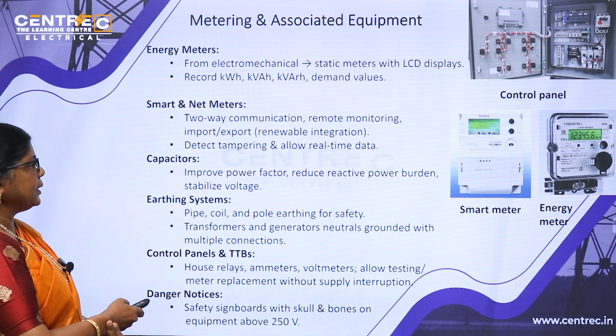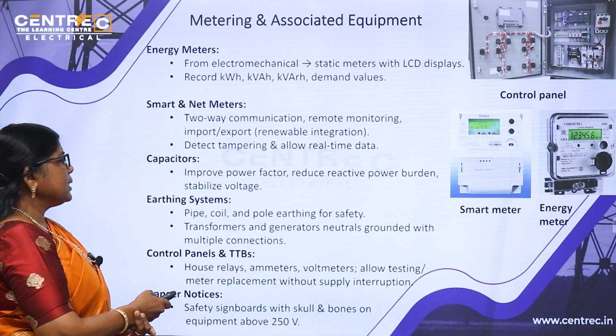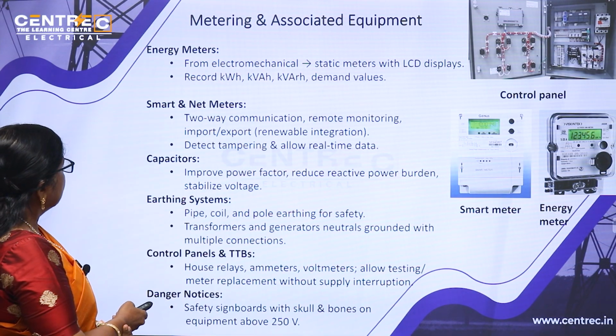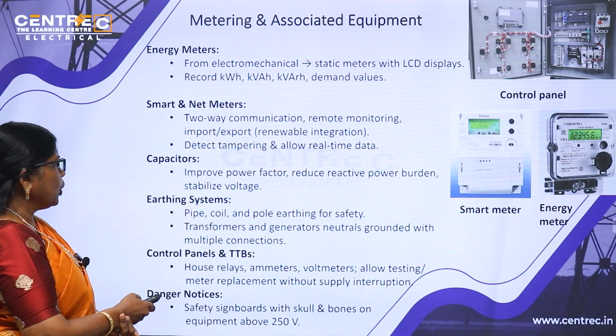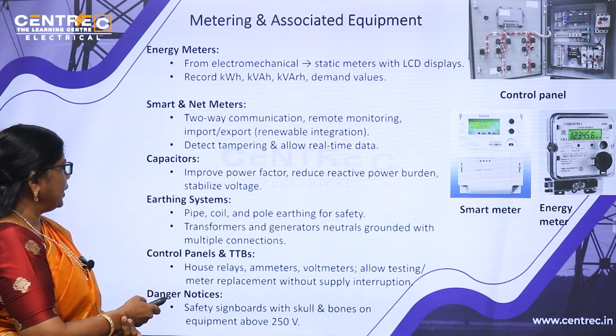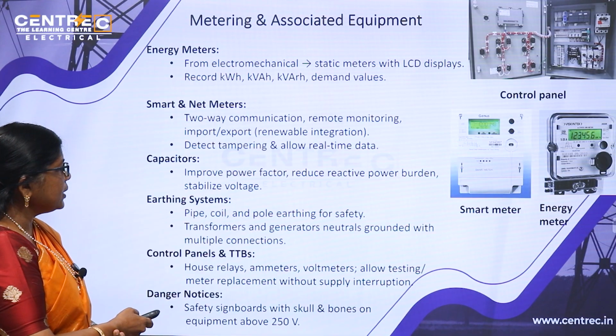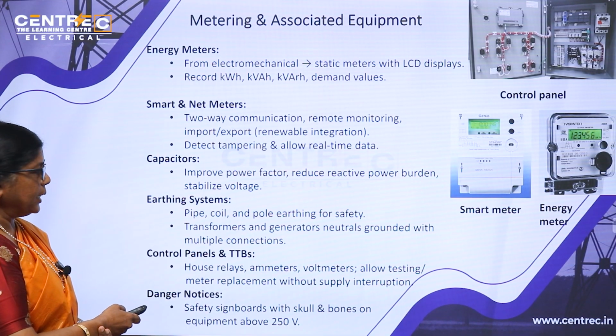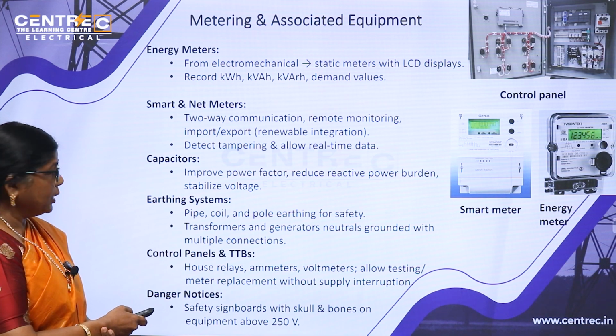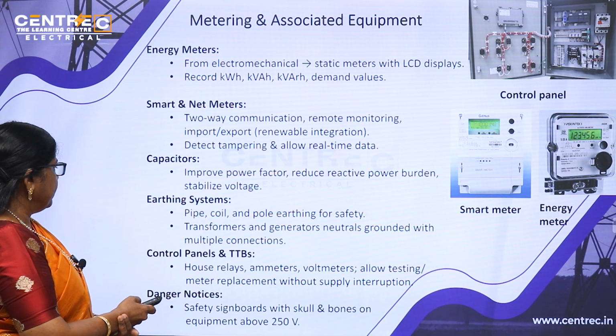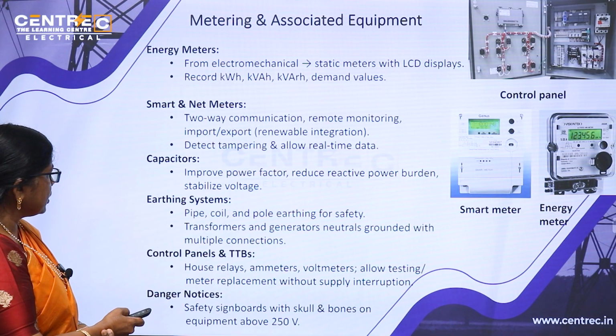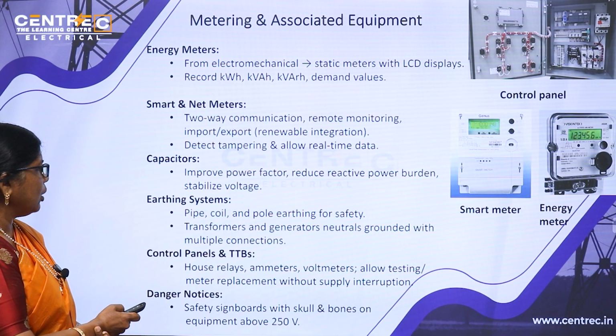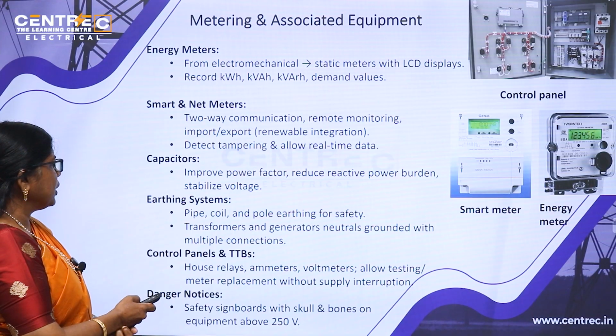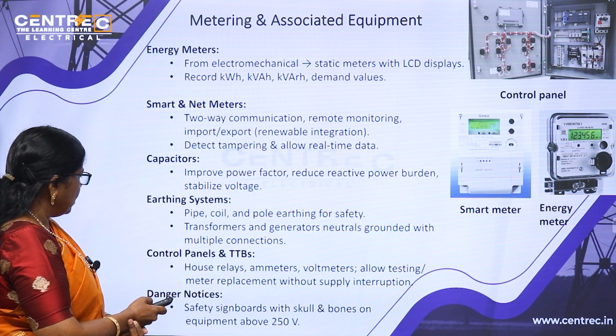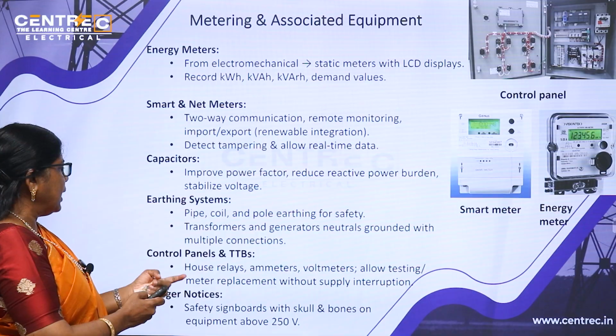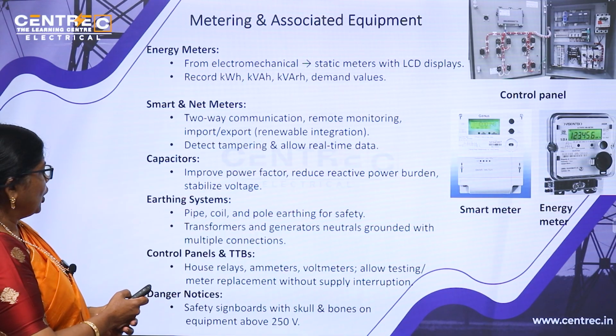Capacitors improve power factor, reduce reactive power burden, and stabilize voltage. Then the earthing system: pipe, coil and pole earthing for safety. Transformers and generators have neutrals grounded with multiple connections. So that is a very important thing for earthing. Control panels and TTBs house relays, ammeters, voltmeters, and allow testing and meter replacement without supply interruption. Danger notice: safety signboards with a skull and bones on equipment above 250 volts.